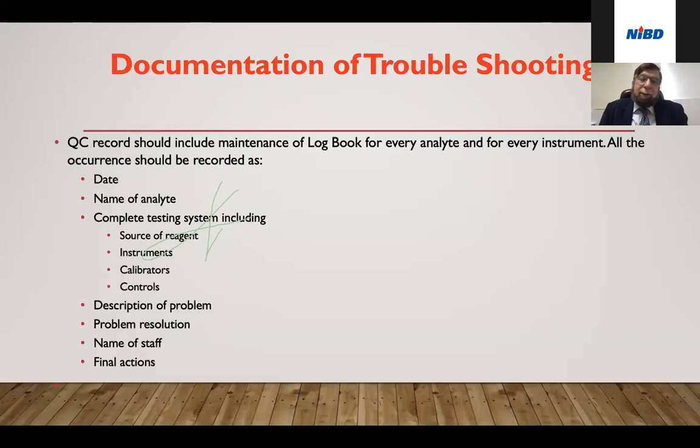and in these logbooks, you should write the date, the name of analyte, complete testing system, source of reagent, instrument, calibrators, controls, and what problem occurred, when this problem occurred, how you resolved it, who did the troubleshooting and what was the final action. It is not difficult.